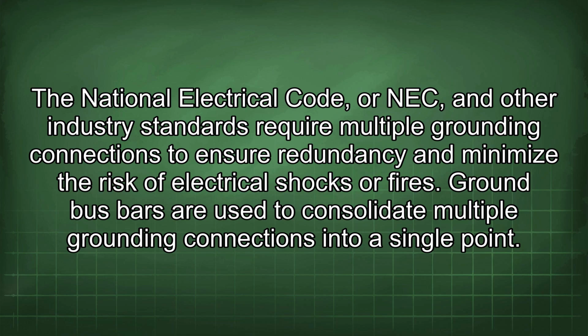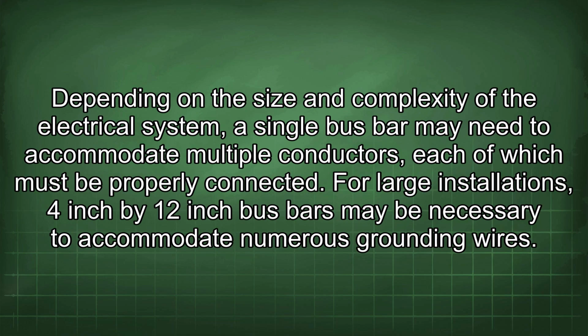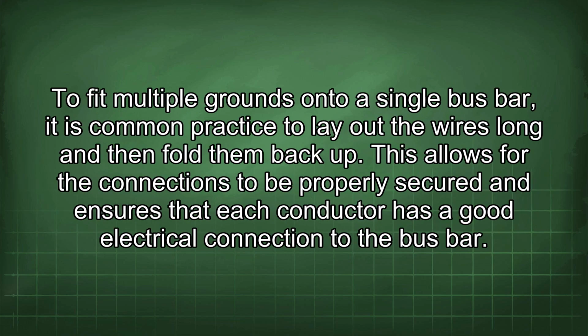Ground bus bars are used to consolidate multiple grounding connections into a single point. Depending on the size and complexity of the electrical system, a single bus bar may need to accommodate multiple conductors, each of which must be properly connected. For large installations, 4-inch by 12-inch bus bars may be necessary to accommodate numerous grounding wires. To fit multiple grounds onto a single bus bar, it is common practice to lay out the wires long and then fold them back up. This allows for the connections to be properly secured and ensures that each conductor has a good electrical connection to the bus bar.